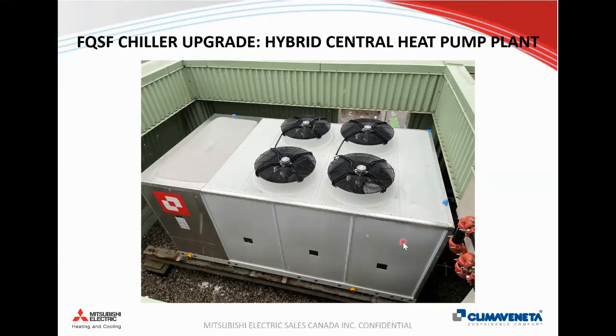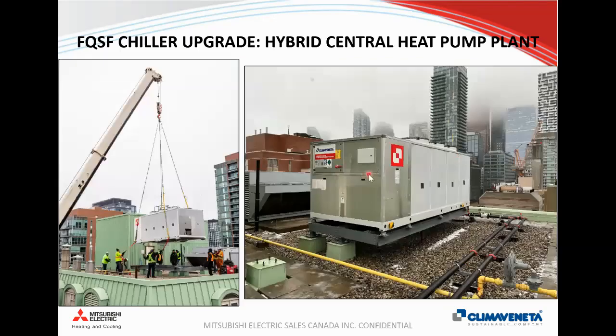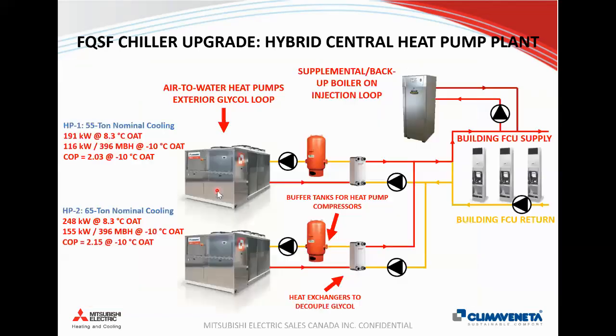So that is one thing with heat pumps. They are larger than typical chillers. That's because to extract heat at -10 or -15 ambient temperature, they need a lot of surface area on the coils for the refrigeration circuit in order to actually pull in that heat. So they are larger. So we had to make room on the upper roof for the second unit to be placed, and just have a photo here from crane day.